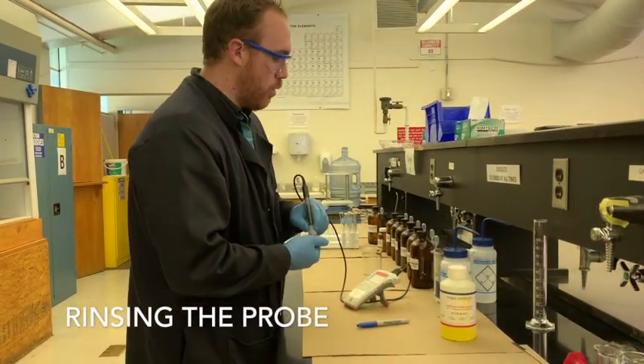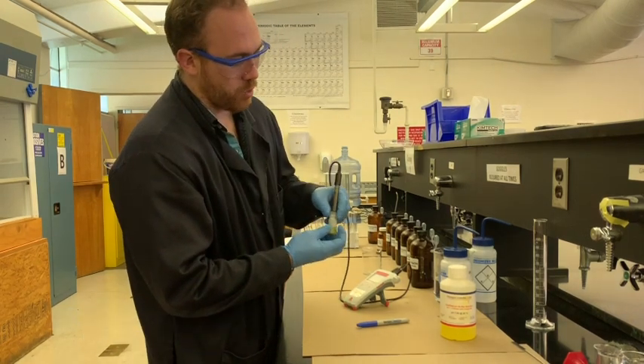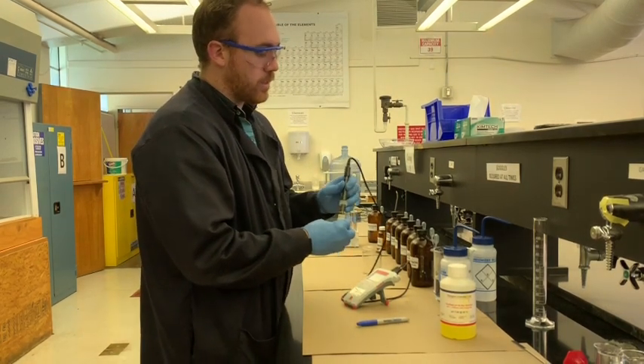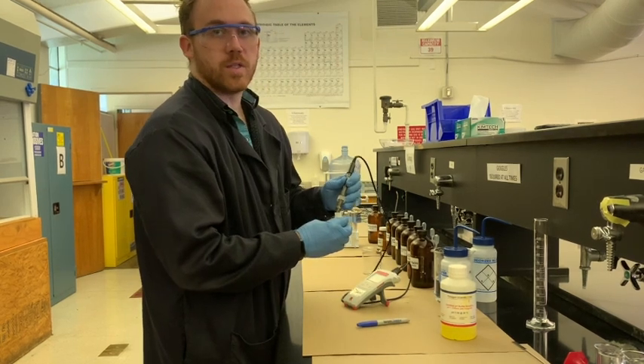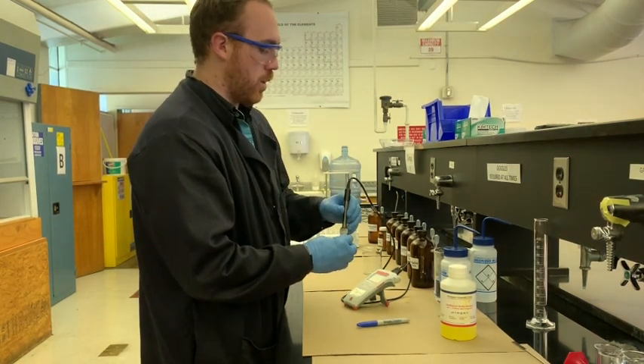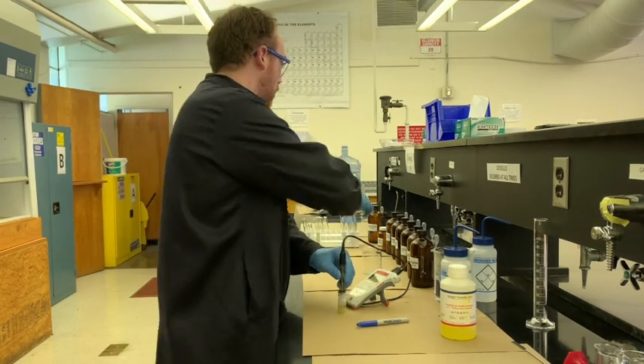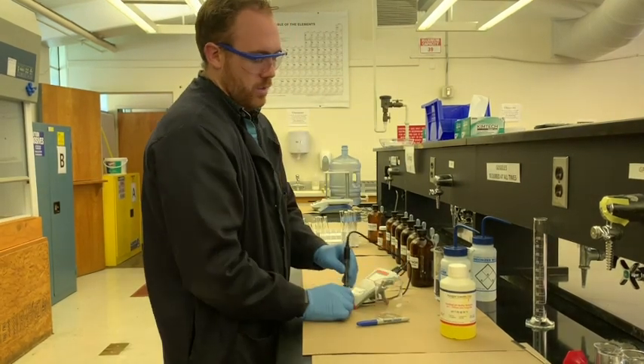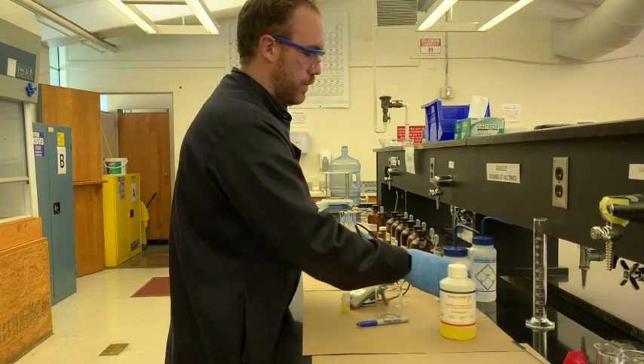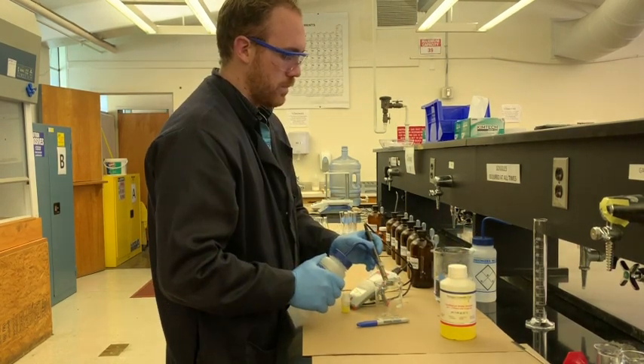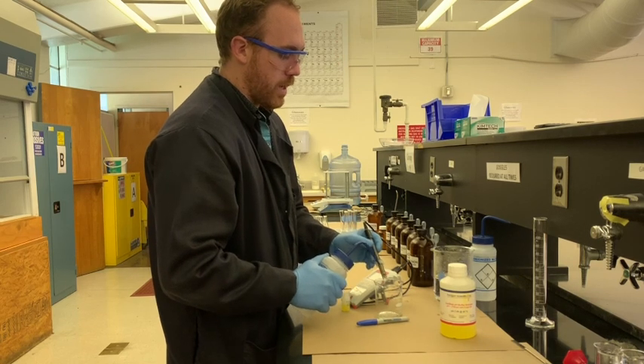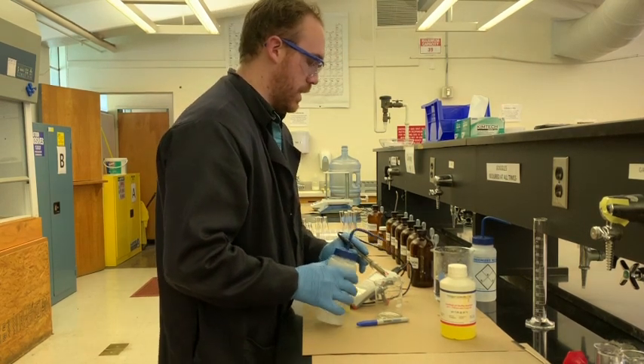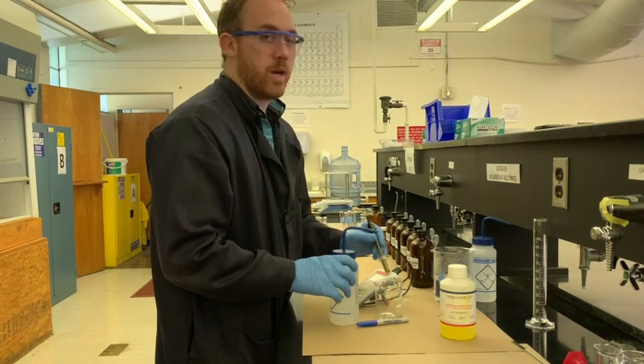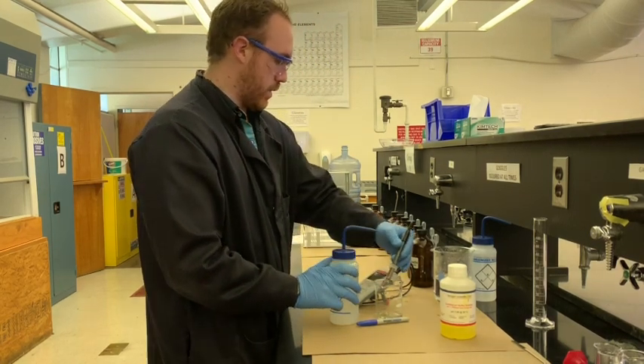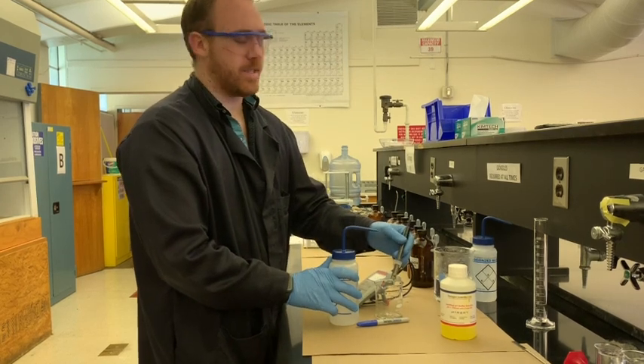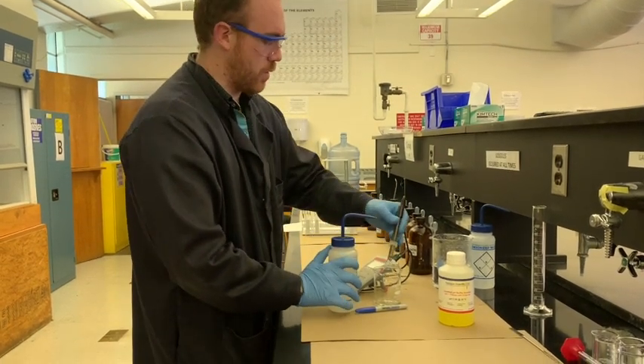Once you remove the solution that you're storing the probe in, it's not the kind of solution you'd want in all of your other solutions that you'll be measuring. So you rinse off your probe. This particular instrument has a setting which allows us to see whether or not it has already been calibrated, which in this case it has, and a little smiley face informs us that it is not in need of a new calibration. So we're going to just get going.